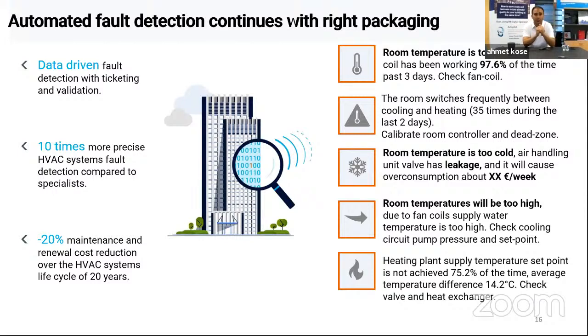Other information: everything is again mechanically working, but because of some sort of leakage there will be problems. This leakage may also show up when we follow the supplied air temperature, it never achieves the target, and everything should look fine. You cannot see it from the BMS, but the actual problem is a leakage in the valve, and then it never reaches the set point.